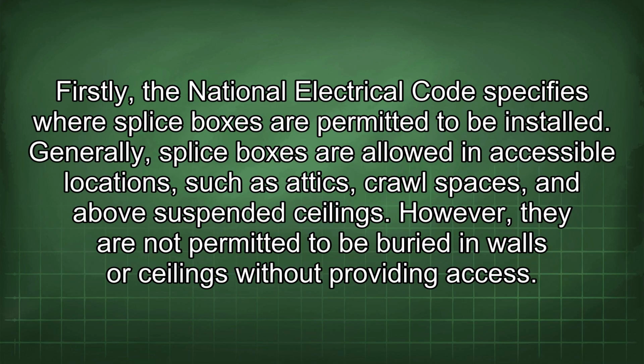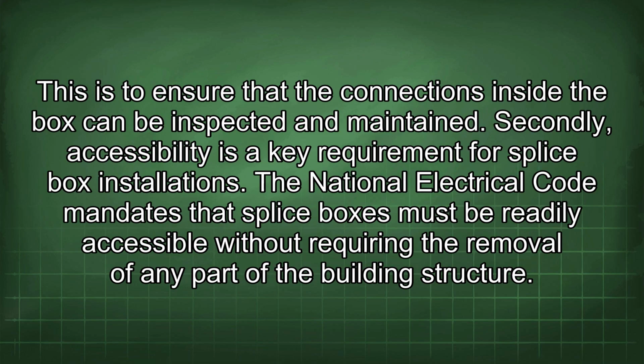Firstly, the National Electrical Code specifies where splice boxes are permitted to be installed. Generally, splice boxes are allowed in accessible locations such as attics, crawl spaces, and above suspended ceilings. However, they are not permitted to be buried in walls or ceilings without providing access. This is to ensure that the connections inside the box can be inspected and maintained.